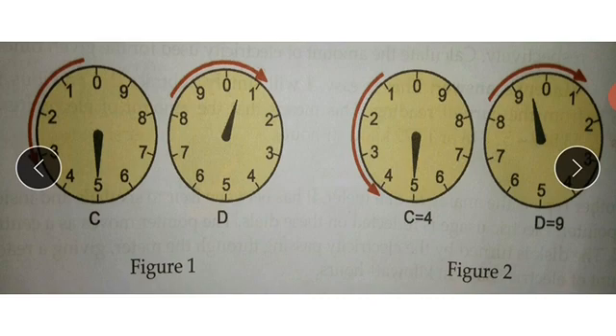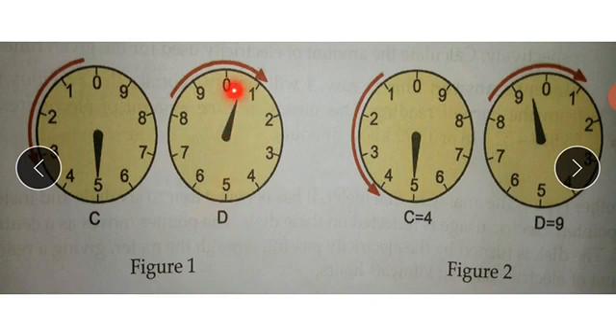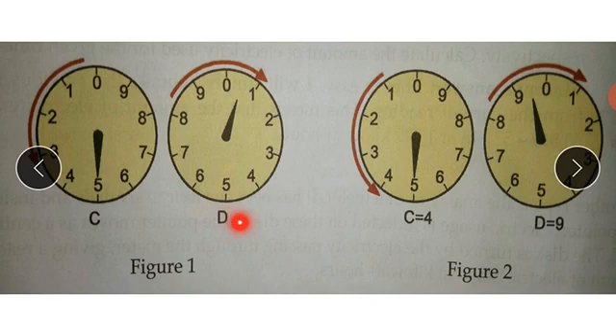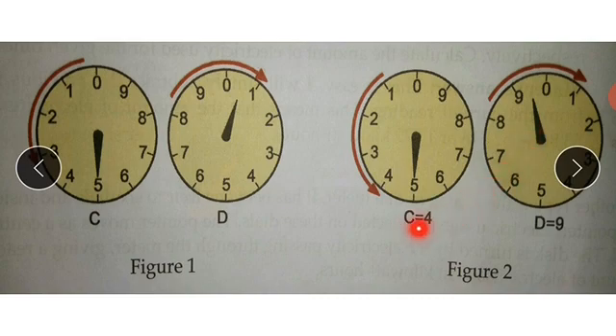To clarify the difference: if the pointer is directly pointing to a number, look at the next dial. If the next dial is on or just past zero, read the number as is — so C is five and D is one. But if the next dial is pointing between nine and zero, it has not yet passed zero, so read the lesser number: C is four and D is nine.